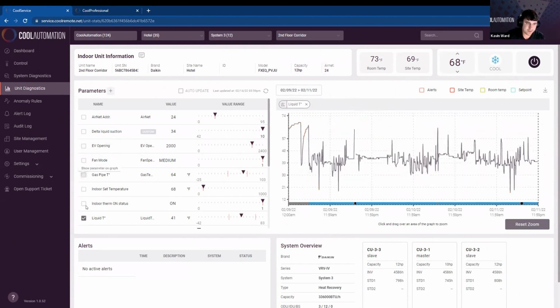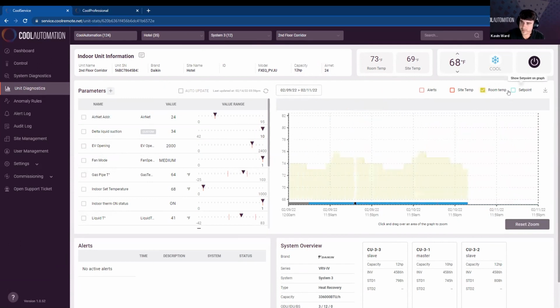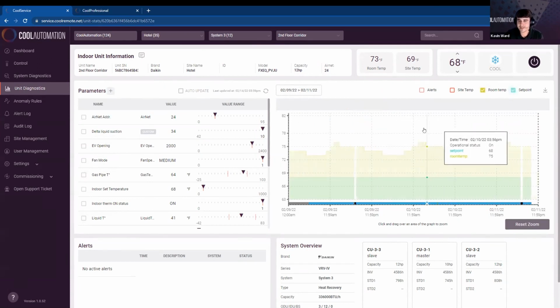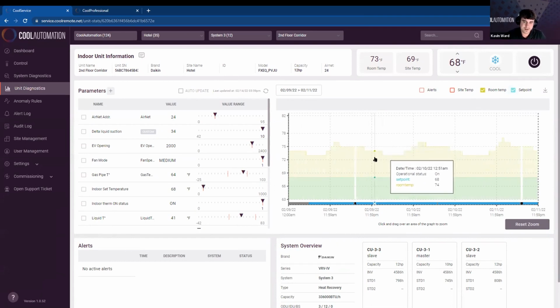But just to give you a good look at a simple way to identify the issue in the space, you can overlay the room temp and the set point. Ultimately, it is pretty clear that there is an issue with this system. With the set point set to 68 degrees, the system is in cooling, but is only 74 degrees in the room. So from a diagnostic perspective, we want to select certain parameters to identify why this system isn't performing.